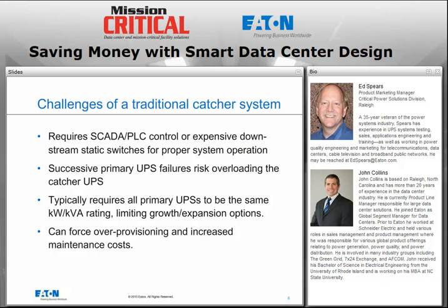As we mentioned on the previous slide, if I have a traditional catcher system and I have more than one primary UPS fail, I do run a significant risk of overloading the catcher UPS. The catcher UPS is usually not, for example, 3 times the size of the primary UPS, so I have to be careful that I don't suffer a disaster scenario where multiple UPS failures would cause the catcher UPS to become overloaded and then it would transfer to bypass.